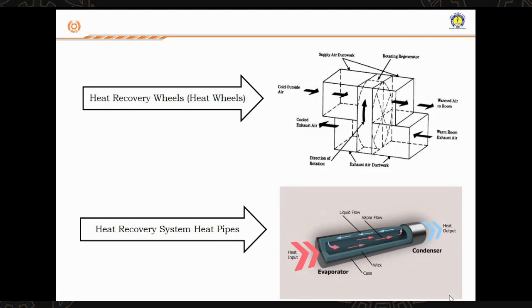Heat recovery wheels are very efficient. There is a slide with a picture showing this; you can just see, I'm putting my cursor. The warm exhaust air is going out of the room, so you require heating inside. Then when the ambient temperature is low, you are trying to take the ambient air inside your room. So you just have a rotary type wheel, where this wheel rotates. Some portion, 50% of the wheel, is open to the room exhaust air, and the other 50% of the wheel is open to the outside air coming inside, right?